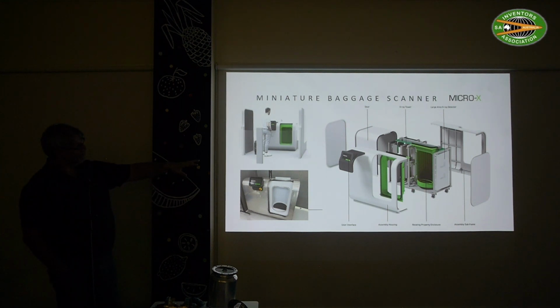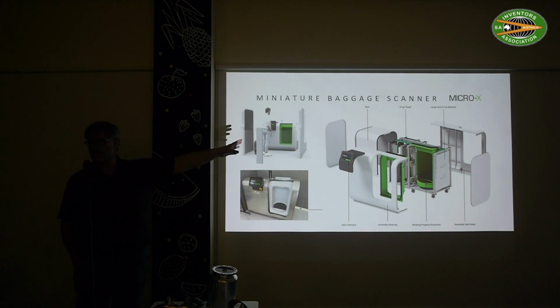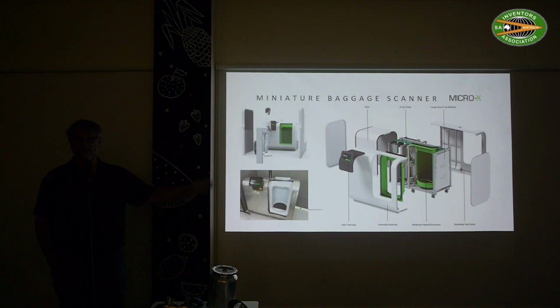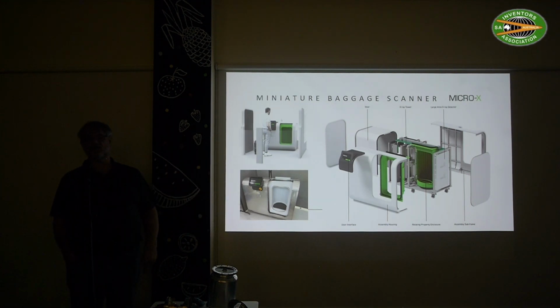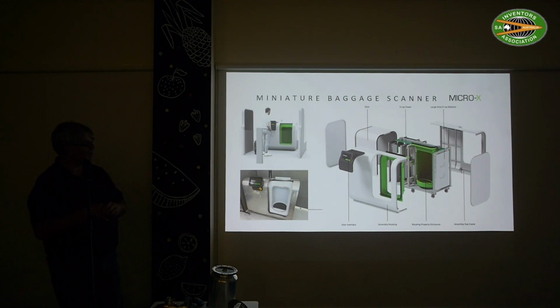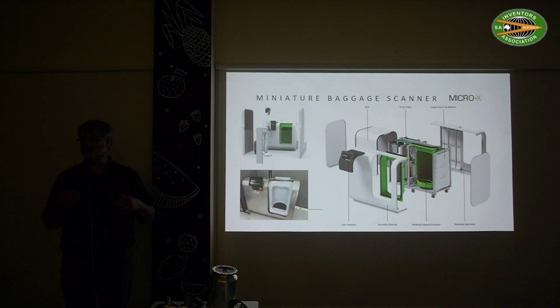And then there's the X-ray tubes, and there's the bin, and there's the detector, and then we have all these covers, and all these covers are completely lead lined, and the door needs to move, and that's one of those interesting things where we said, holy dooly, this door is about 100 kilos. How are we going to move this in a way that is safe without cutting somebody's fingers off? There are all these interesting little challenges, and in the end we found a controller that is designed to handle elevator doors.